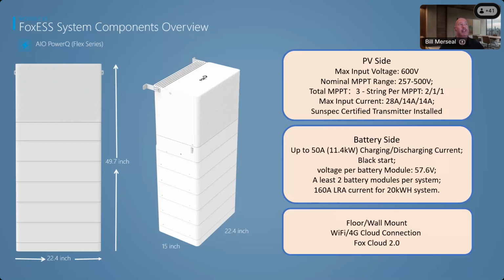When we're looking at your MPPT range, we go from 257 to 500 volts per string. There are 4 strings and 3 MPPTs — the first string is a parallel, that's why you'll see a 2.